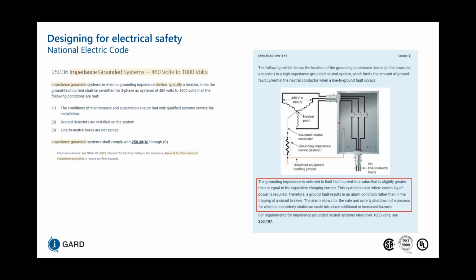This system is used where continuity of power is required, so we can continue the process in the event of the first phase to ground fault, and only alarm the condition of the first fault without having to trip any circuit breaker. So this is becoming more and more popular in industries which cannot tolerate tripping on first fault. And such applications can include, but are not limited to, hospitals, data centers, wastewater treatment facilities, and oil and gas, I guess mining as well.